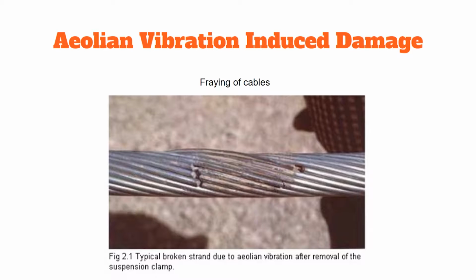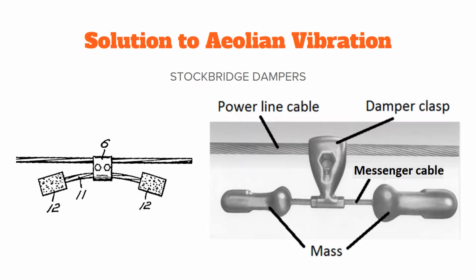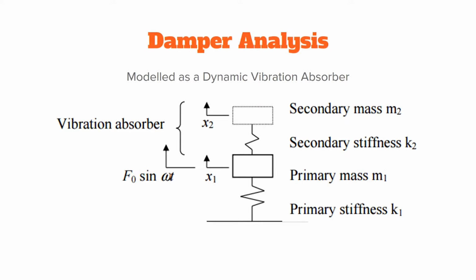For these reasons, power lines must be engineered to be highly durable. However, fatigue failure due to vibration is difficult to prevent purely with intrinsic cable properties. A Stockbridge damper is one way of suppressing this Aeolian vibration to ensure minimal fatigue damage to the cables. The vibration of the messenger cable and blocks absorbs the vibrations from the powerline cable. Modern designs use masses of steel. The powerline cable and Stockbridge damper system is nonlinear. However, simplifications of the system can be made in order to allow for easier optimization of the damper.